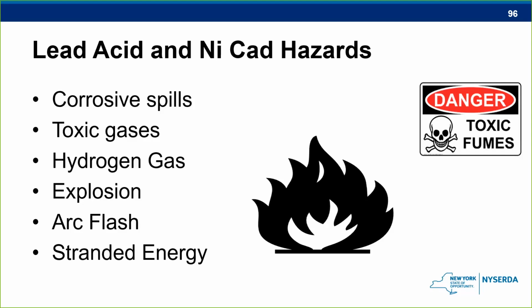And during a shutdown, which Jennifer also mentioned before, we've got to be concerned about arc flash. When we're shutting off a large amount of energy, we've got to make sure that there's no arc flash by just shutting these things down. And there should be some sort of signage there for the firefighters just to warn them about some sort of arc flash that could take place.